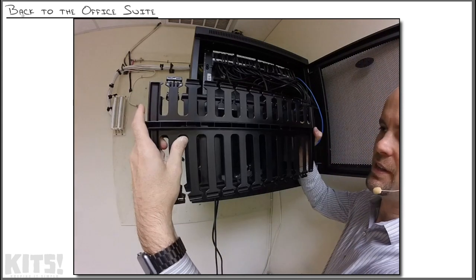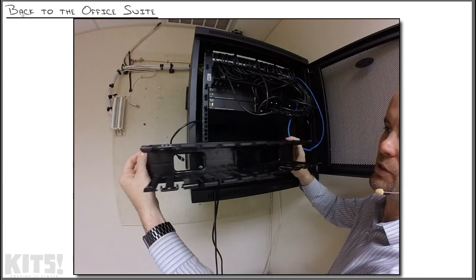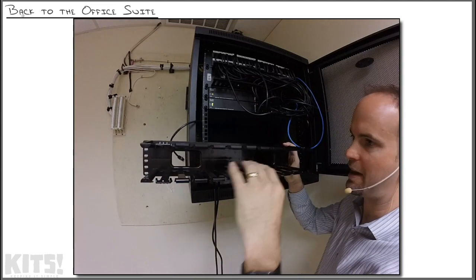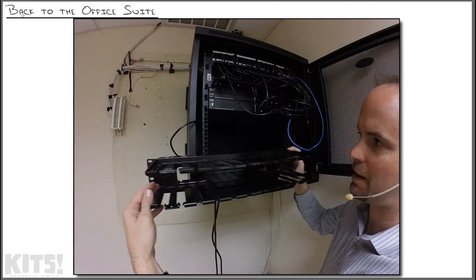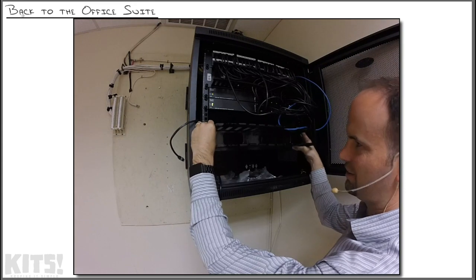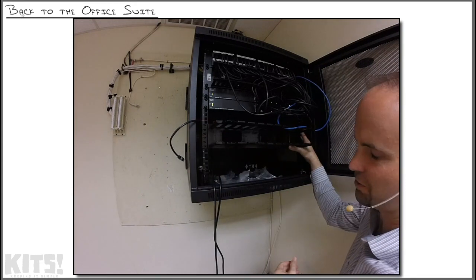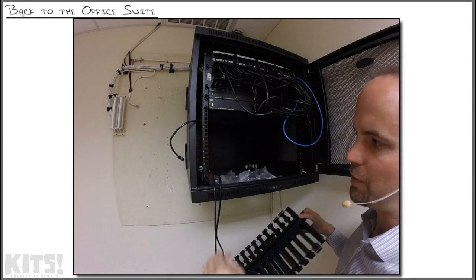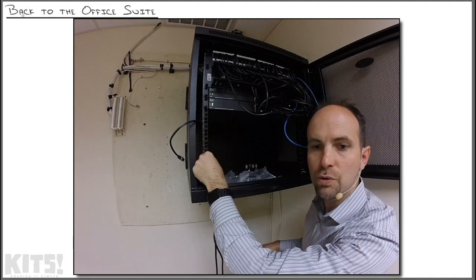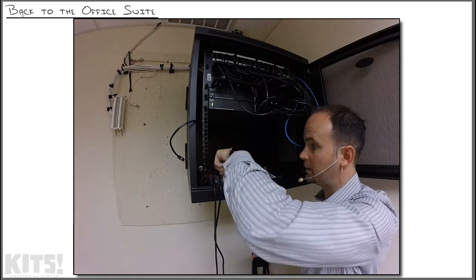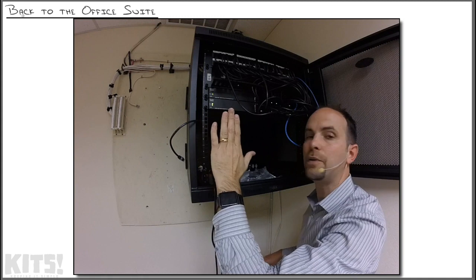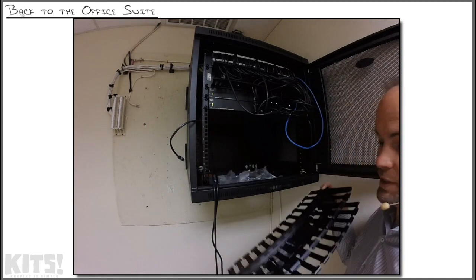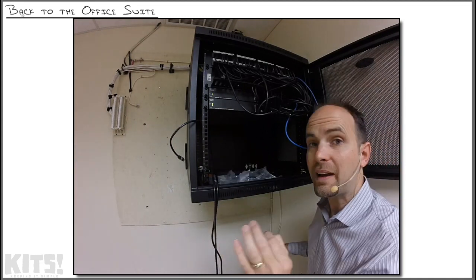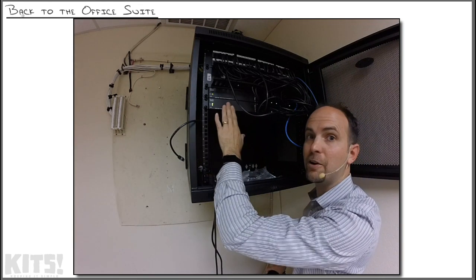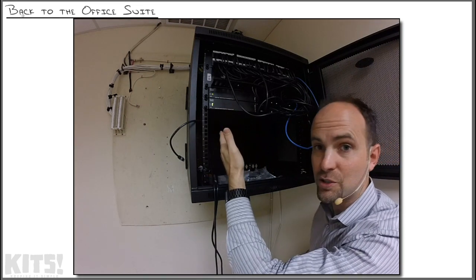But if you look at this, you can actually flip it around and you get this really deep cable management. I mean, a lot of space to shove cables in there. Now, you might look and go, well, obviously that's going to come right out the front of the rack. Well, almost all of these racks that are enclosed like this, you can move the entire frame. So I could literally unscrew this guy and move the whole thing back, which then this would fit in there. The drawback of doing that is then you want to make sure that you have very short devices inside of here. Now, these switches are fine.